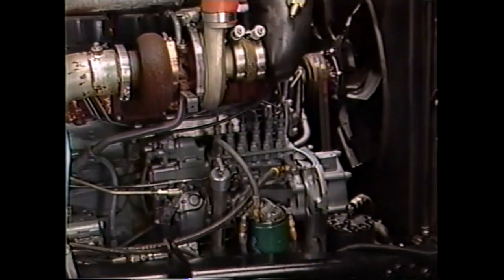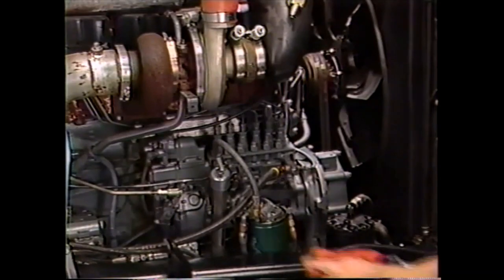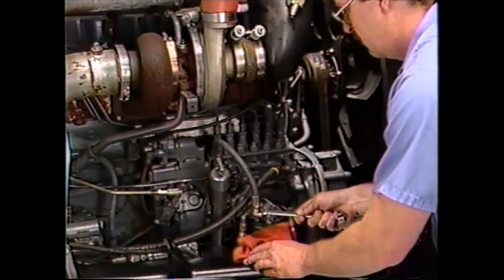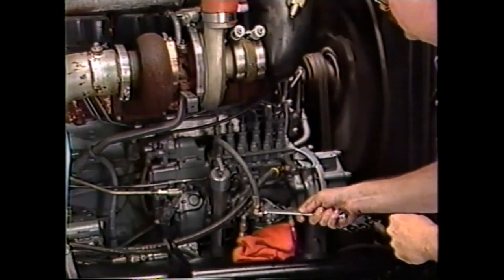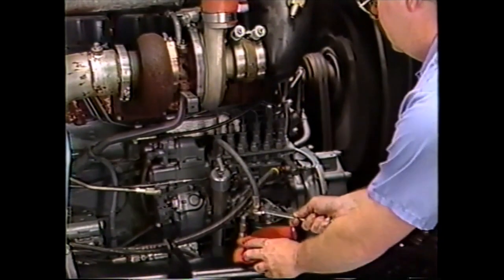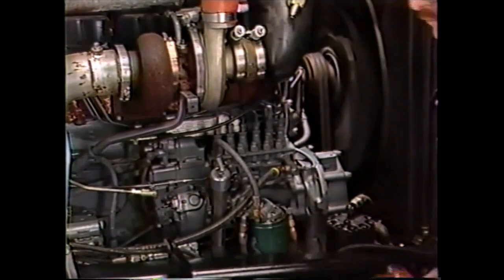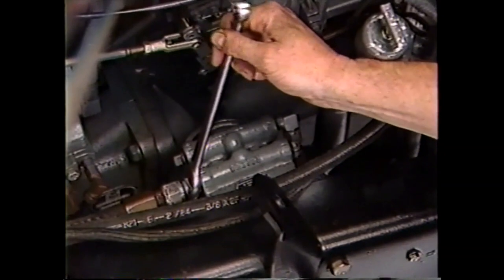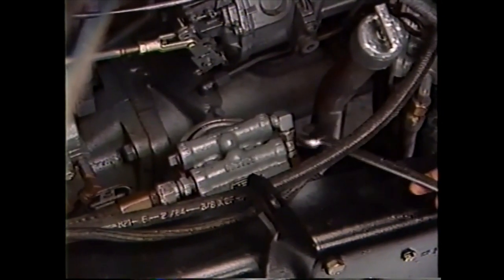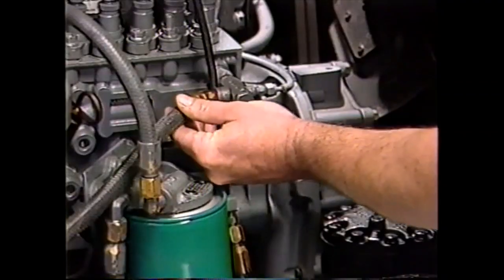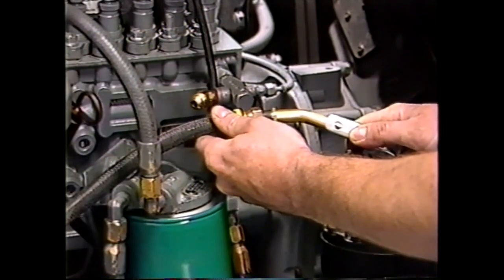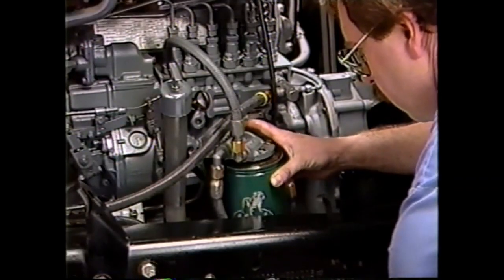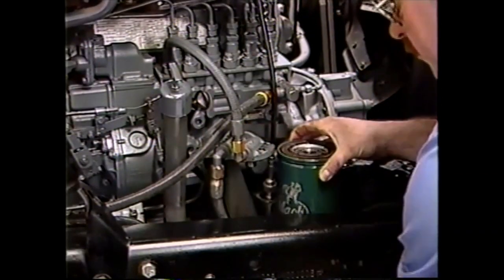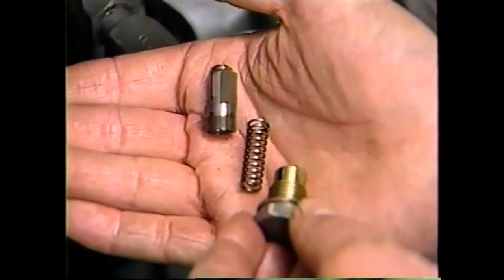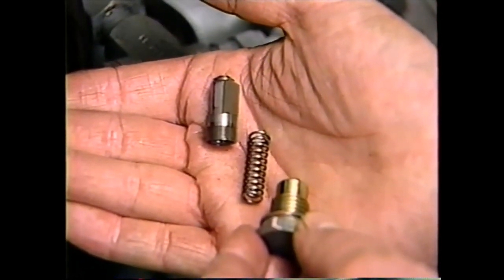If fuel does flow, reconnect the lines and prime the fuel system. Then perform all tests possible from the first troubleshooting procedure we reviewed. In particular, check for suction and pressure side leaks, fuel line restrictions, clogged fuel filters, and a damaged overflow valve assembly.